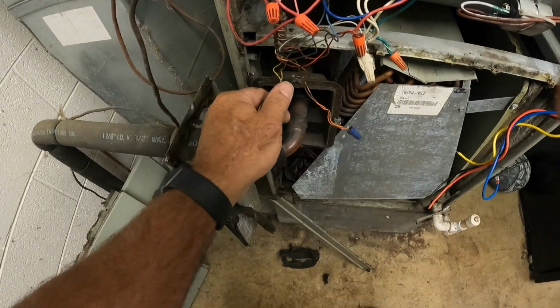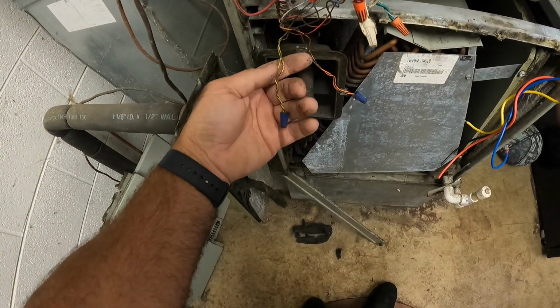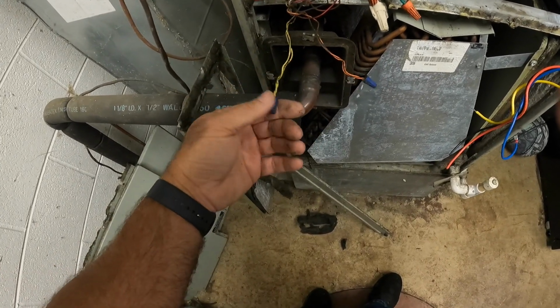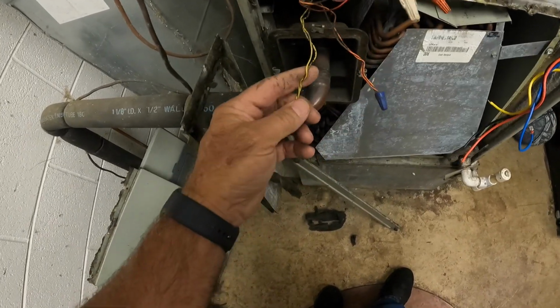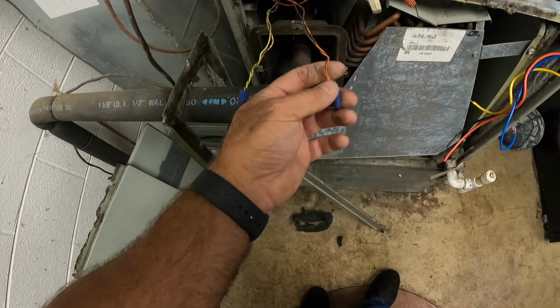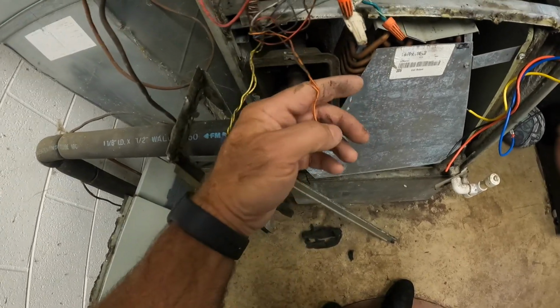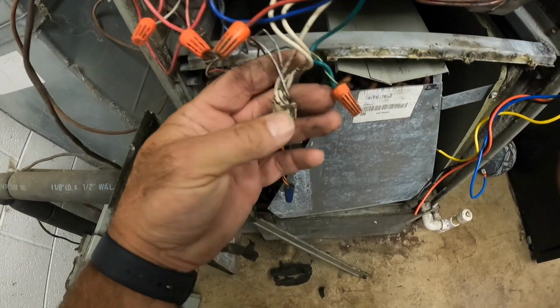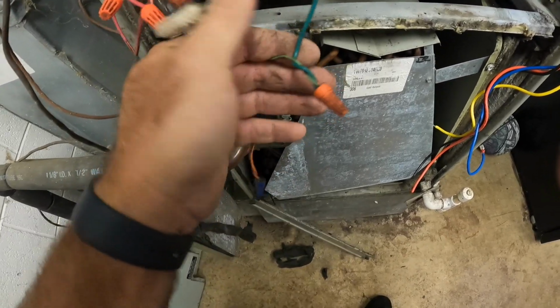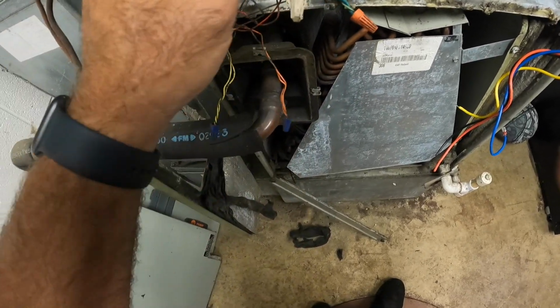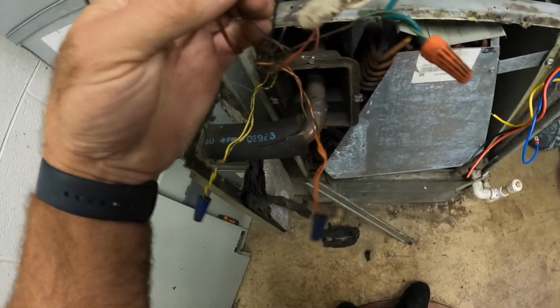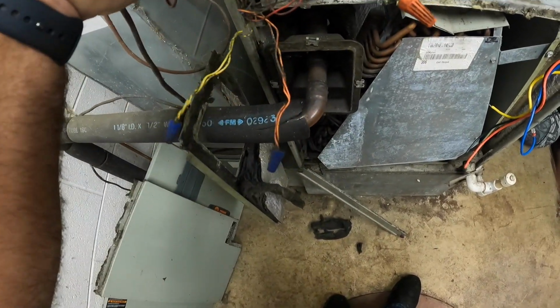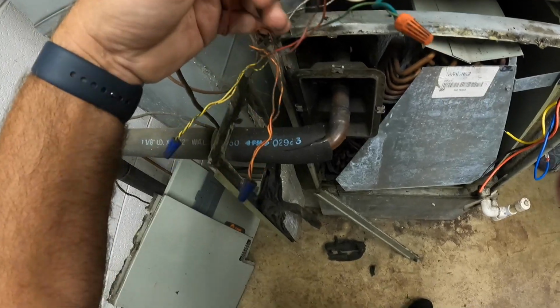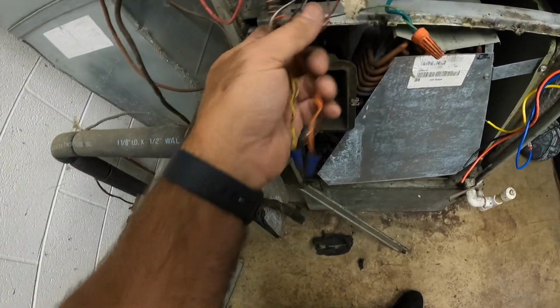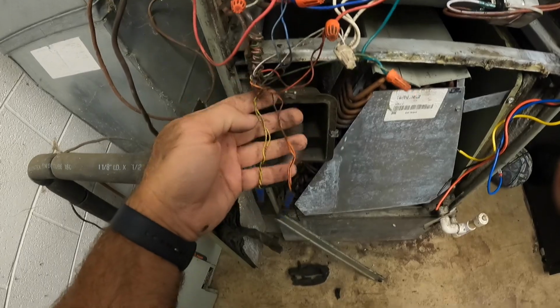I went by and looked at the front end on the building control system at their main office the day before yesterday, and you had a compressor command, which I'm going to assume is yellow. You had a reversing valve command, orange. We had an electric heat, which is the white. We had a fan, which is the green. So of course we got red, common here. So it should be straightforward. Normal colors, blue for common, everything else is just like you'd normally hope to see. So I'm going to get this unhooked.